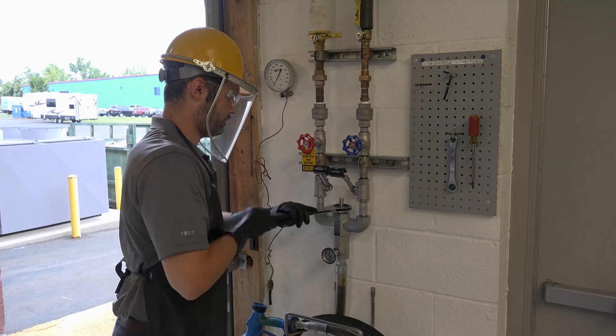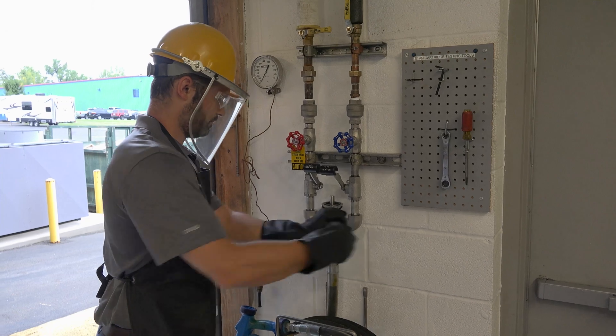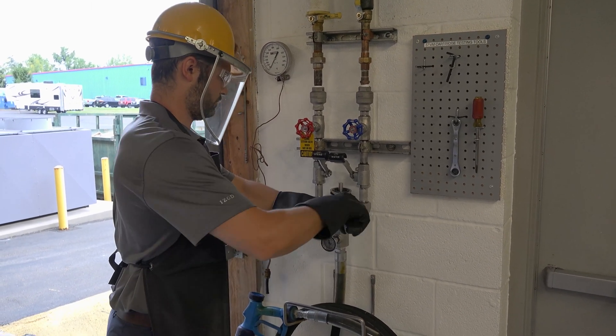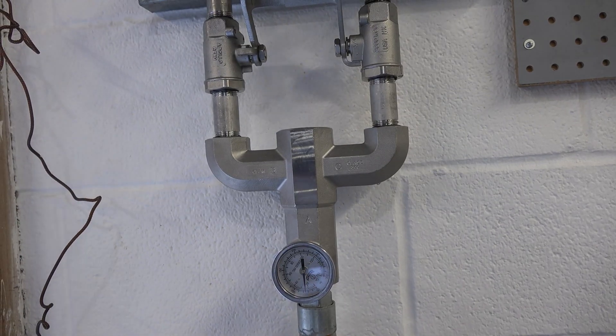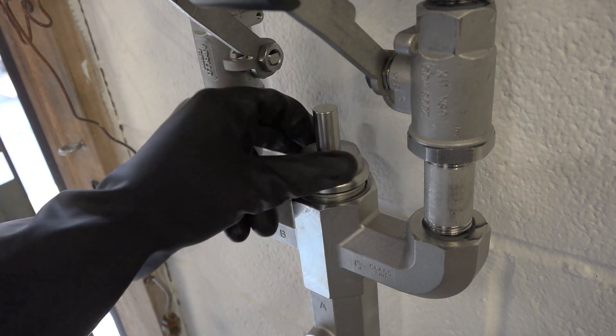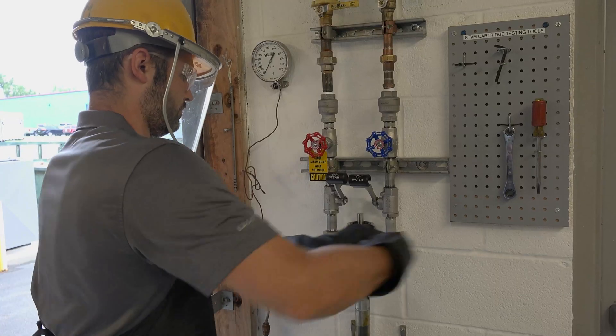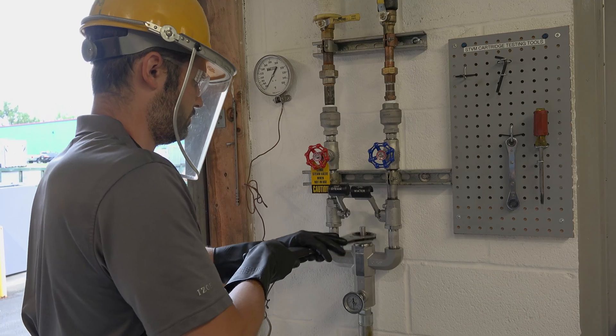What makes the STVM station stand out from its competitors is the ease of maintenance, which is critical to minimizing downtime in a production facility. The replaceable cartridge design allows for quick and easy in-line maintenance. Simply remove the STVM cartridge with a wrench at the point of installation and replace it with a spare to have the unit back up and running in minutes. This saves significant time and money traditionally spent on operating downtime and labor costs.